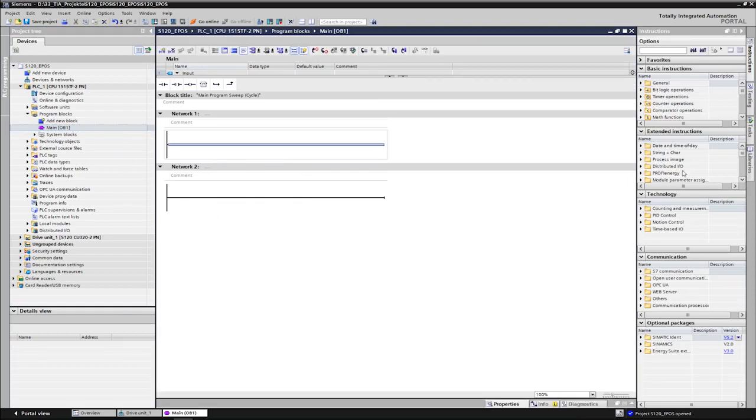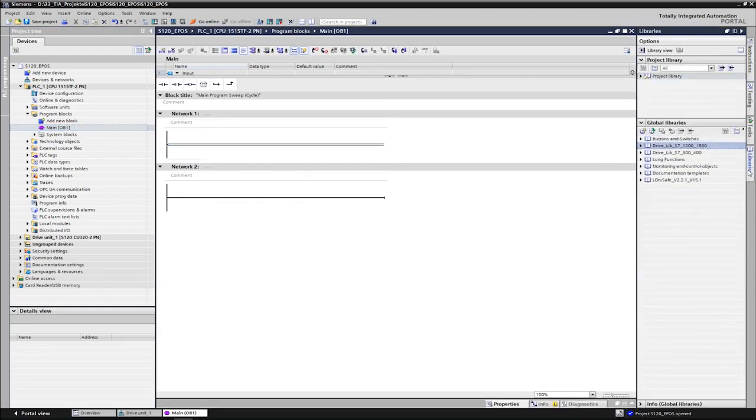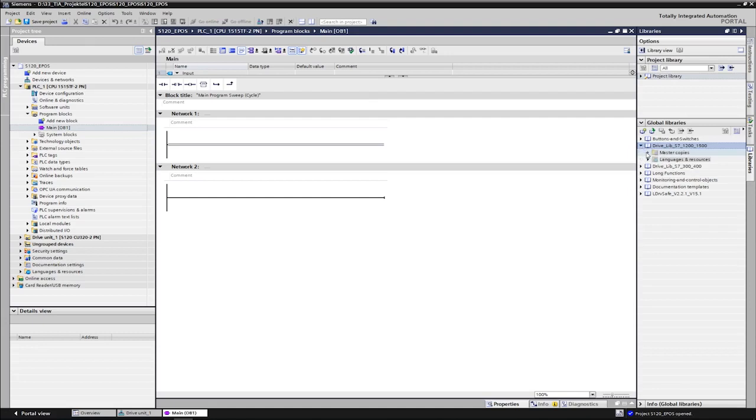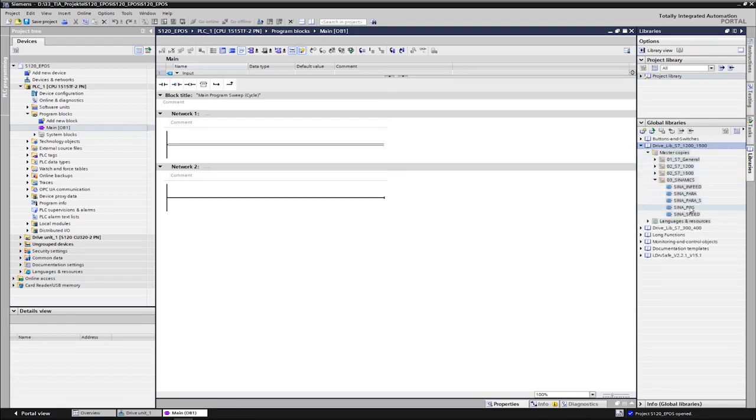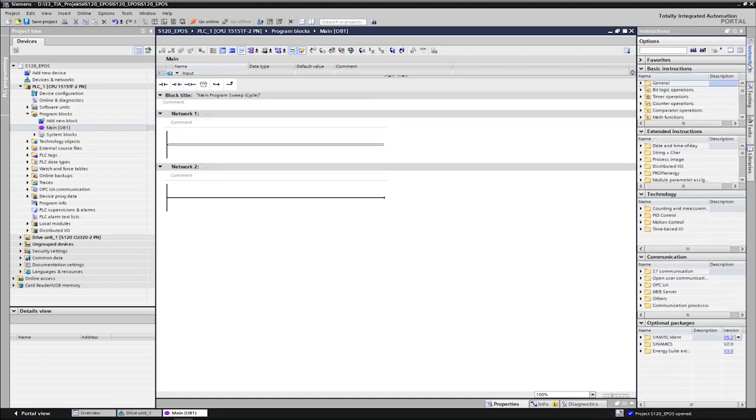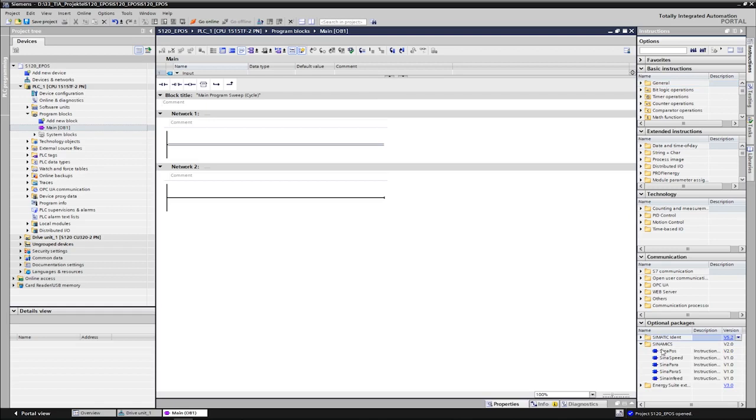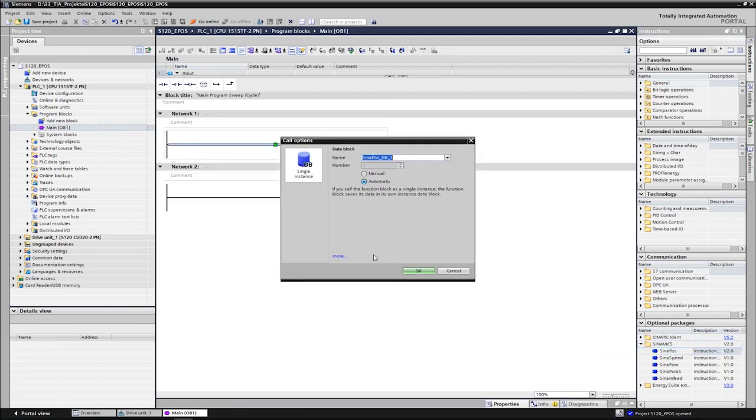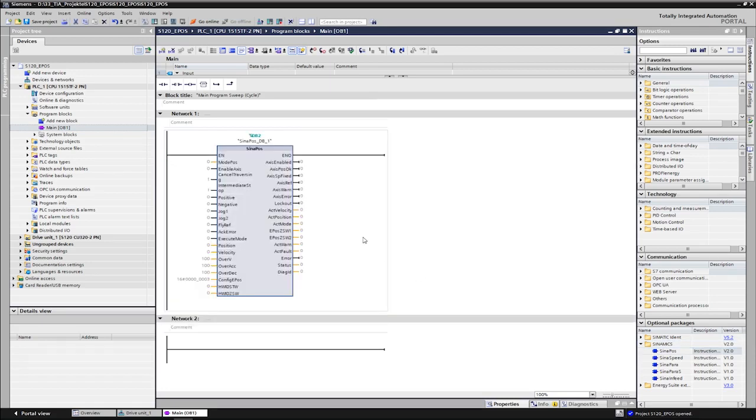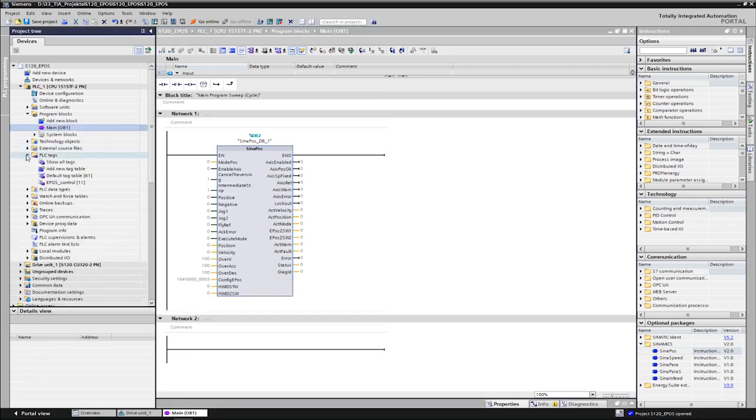The SinaPos function block can be found under the global libraries in the pre-installed drive lib or in the instructions under optional packages. We call the block in the cyclic OB1 program via drag and drop. An instance DB is created here. In order to observe and control the SinaPos block later in the program, the input and output data are interconnected with global tags which have already been created here in the tag table.